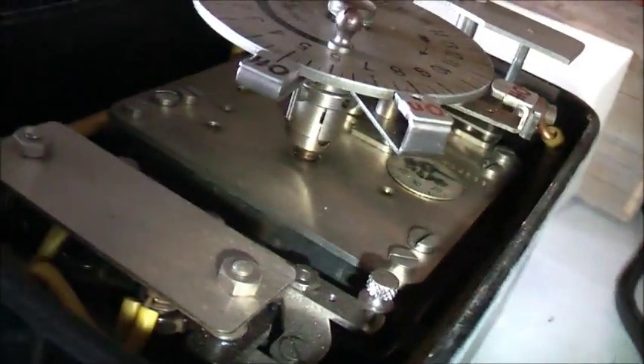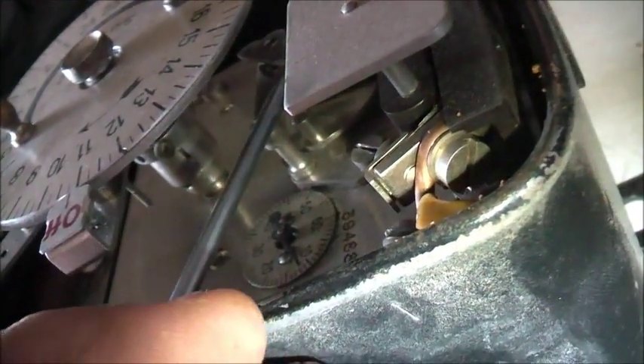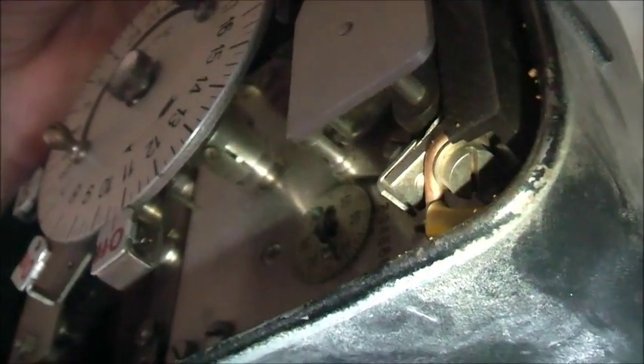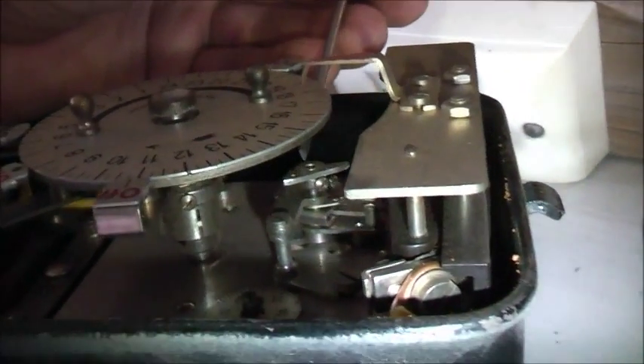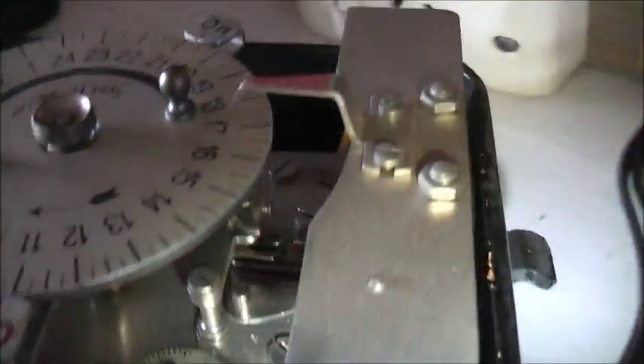Looks like a proper watch, well-built. It's got little things you screw in there. This must come off and that screws into one of these I think - so it's a special trigger for something. When it hits that, it closes the contacts and opens it. The off one is further down - it goes down here. I would need to hit behind there to turn it off. Pushes up behind there and the on one comes around, hits on this end, closes it, and that turns it on.